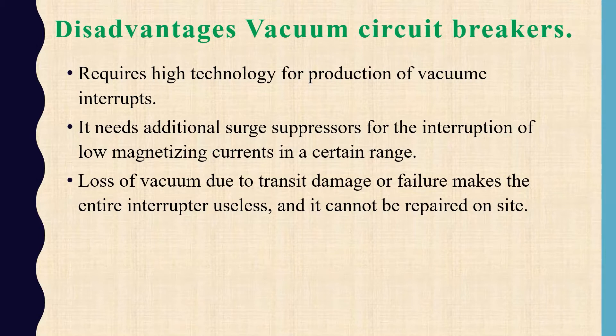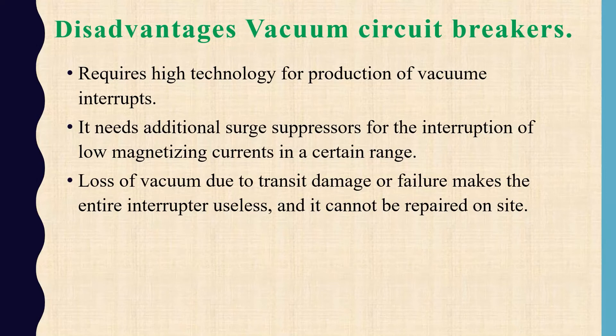The disadvantages of the vacuum circuit breaker: first, it requires high technology for production of vacuum interrupters - high technology is needed to manufacture this circuit breaker. Second, it needs additional surge suppression equipment for interruption of low magnetizing currents in certain ranges. Third, loss of vacuum due to damage or failure makes the interrupter useless - if the cylinder or bottle loses its vacuum and air enters accidentally, the entire device fails and cannot be repaired on the spot.